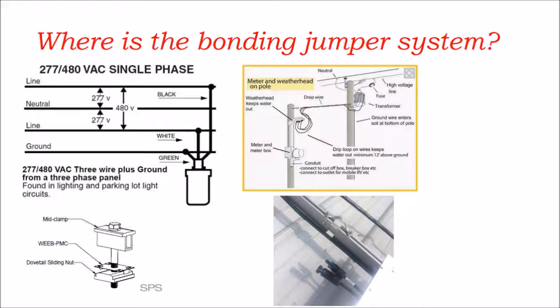And so what we see down in the middle lower picture is a grounding washer between two pieces of rail. Now there's a stick of metal, right smack dab in the middle of these two pieces of rail, and that piece of metal is there to splice the rails together and turn them into one rigid piece of rail instead of two separate pieces of rail. But that splice is not listed as a ground path. And so here we have a separate bonding jumper that bonds the two pieces of rail together. And that's another thing: just because it's metal touching metal doesn't mean that it actually qualifies as a ground path.